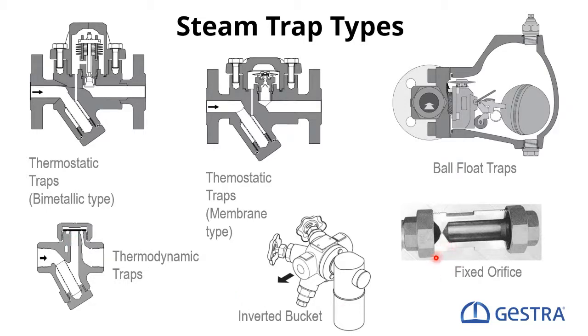Orifice steam traps are some which have backing up of condensate. If they are designed in the wrong way, they can work correctly for a very short moment, because then the operating data changes and we have a loss of live steam, because we have summertime or not a process anymore, and so I don't consider these steam traps too much.